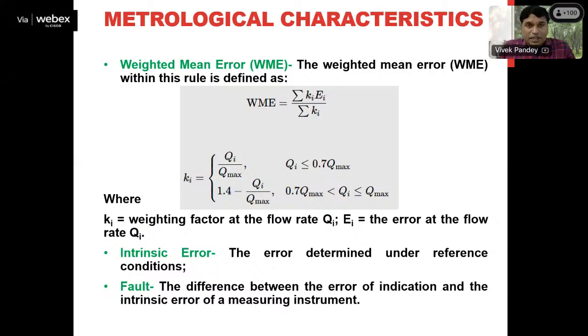Now the next section which I will be discussing in the gas meter is the metrological characteristic. In metrological characteristic, the first parameter I am going to discuss is the weighted mean error, a very important parameter which ensures the accuracy of the gas meter. And what is this weighted mean error? Basically, it is just like when we try to find the measurement error of any measuring instrument. Usually, whenever we calculate the error in measurement by a measuring instrument, we compare the indicated value with some reference quantity and we get the percentage of error. Fine. That is basically the accuracy check, or the error in the accuracy of the measuring instrument. That error we will also try to find out during the verification of these gas meters.